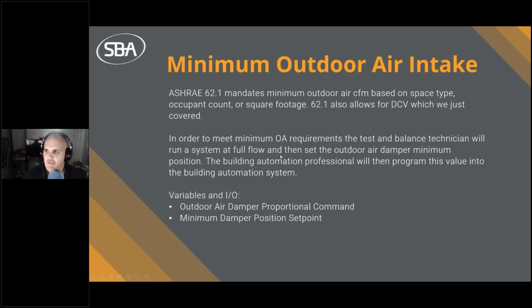So ASHRAE 62.1, if you haven't heard about it, is a standard that dictates the minimum outdoor air CFM based on space type, occupant count, or square footage. There's a table, I think around page 70 of the standard, about two-thirds through, and it lays out a bunch of different space types. It says based on CFM per occupant, CFM per square footage, or just a round space type number, this is the minimum outdoor air flow, and this is the minimum overall flow.